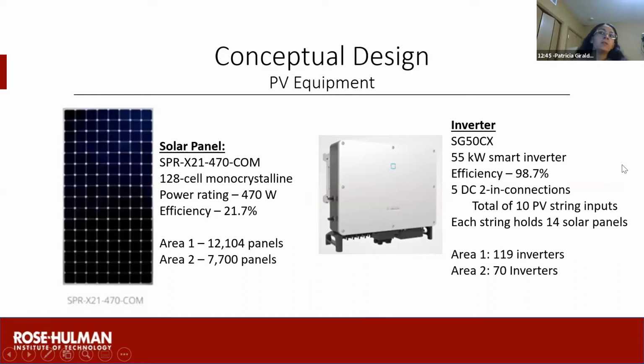So solar panels and inverters are the most important components we needed to generate the solar energy. So we chose a solar panel on the left because of its super high efficiency, which is around 21.7%, and the high output power of 470 watts, and it has a pretty low cost per watt. And the inverter we chose is there on the right. The main reason we chose that one is because it has a large number of solar panels it can handle, which is around 140, since it does have 10 PV string inputs. So the team used a total of around 19,804 panels, with 12,104 being in area 1, 7,700 in area 2.